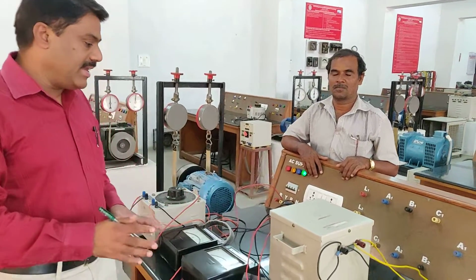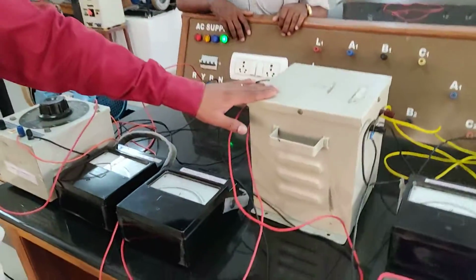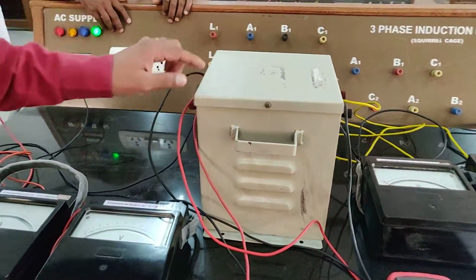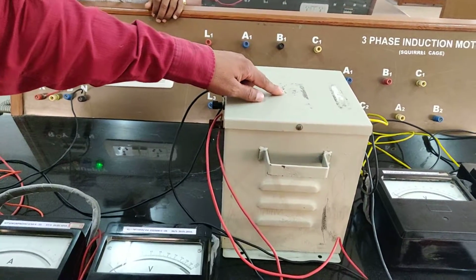For that, we need a transformer, which is the one under test. We are going to test this transformer. It is a 2 kVA transformer. In the primary side, I have connected 230 volts - this is the primary side, otherwise called the HV side. In the secondary, I am going to have 115 volts, that is the low voltage side. The rating of the transformer is 2 kVA.